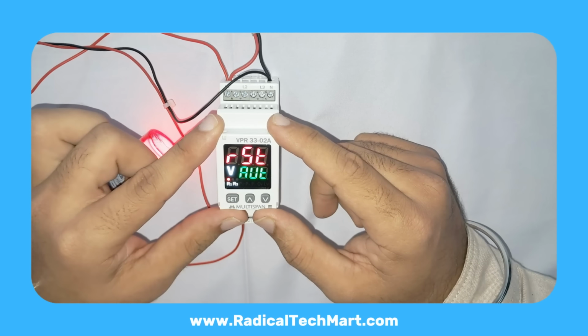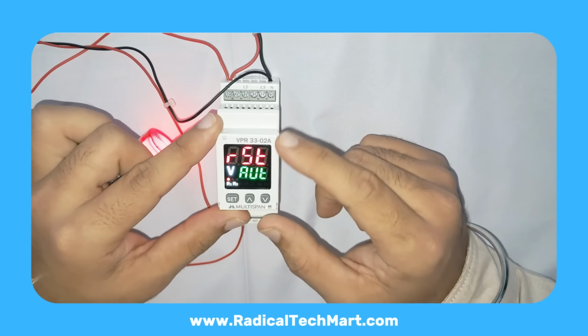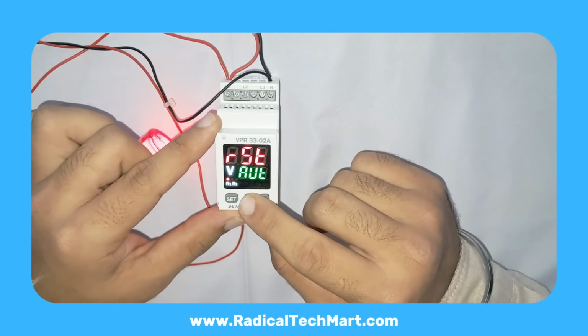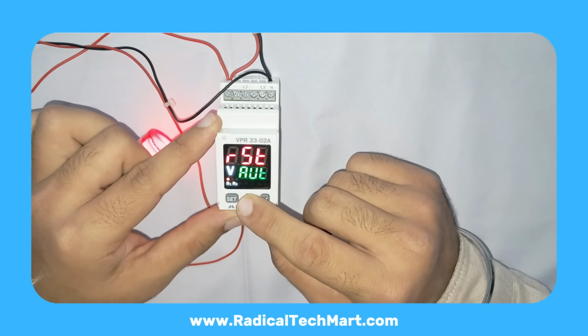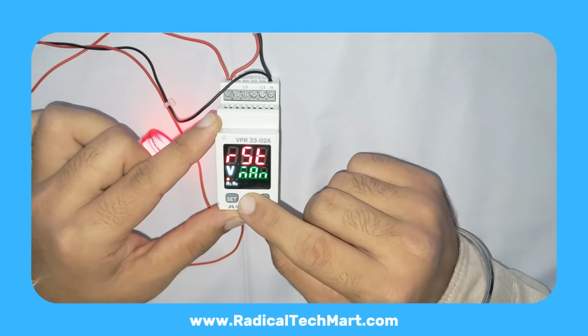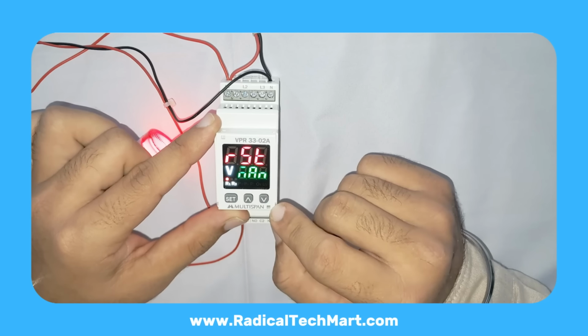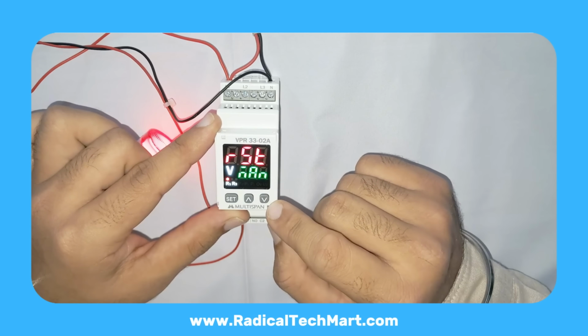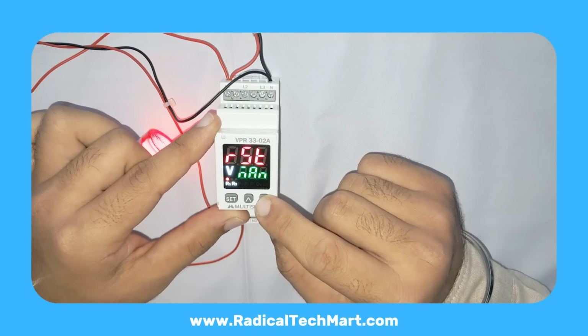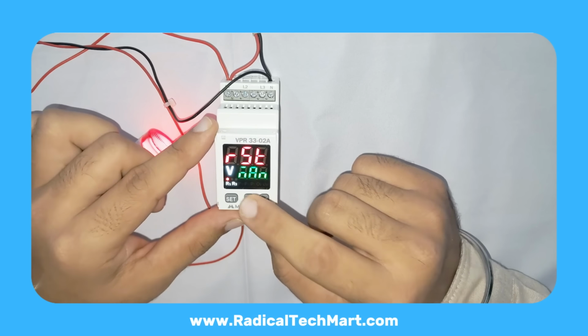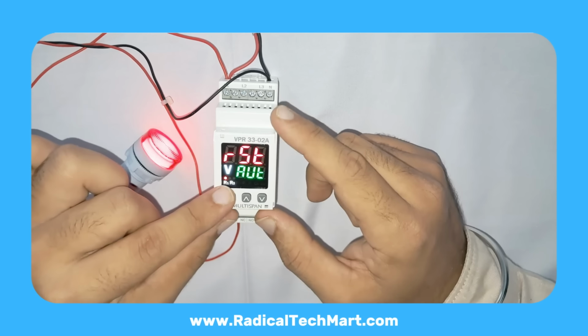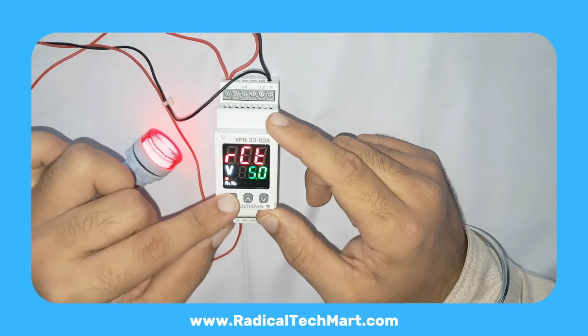Reset mode, auto or manual. Next is reset mode, auto or manual. If you select manual, whenever a fault occurs and clears, you will have to manually reset the relay by pressing the down button. If you select auto, the relay will automatically reset once the fault condition is cleared, based on hysteresis and recovery time. Press Set.